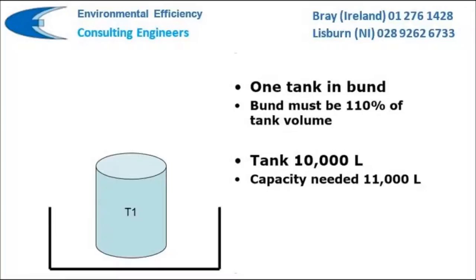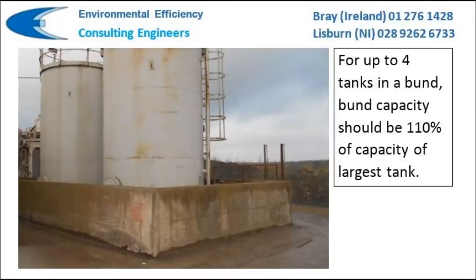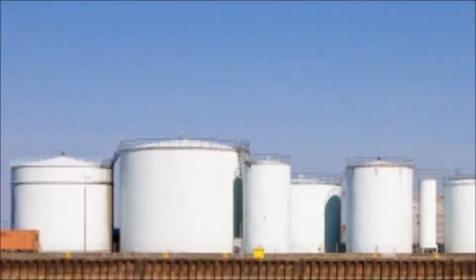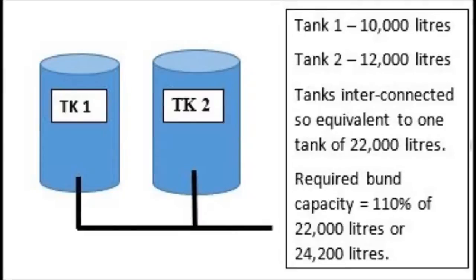If there is only one tank in a bund, the general rule simplifies to requiring the bund capacity to be 110% of the tank, as this is clearly greater than 25%. For 2, 3, or 4 tanks in a bund, the 110% rule still applies as this will always be greater than 25% of the total. For more than 4 tanks, 110% of the capacity of the largest tank needs to be found and then compared to 25% of the total tank capacity. Whichever quantity is the greatest is the required capacity of the bund.